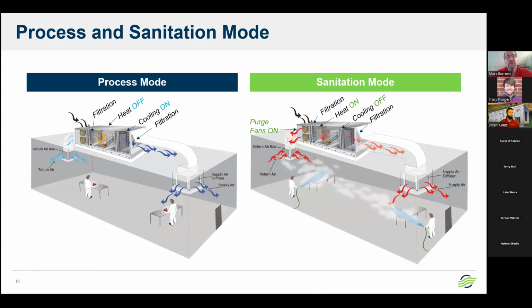So again, the process mode, 5% outside air. We're going through the pre-filter, which is a 2-inch pre-filter. The heating is off. The cooling coil is definitely active, and we're going through the filtration. If you're taking notes on this, on a wet coil, we don't like to go more than 600 feet per minute on the cooling coil. If we go above that, the fear is we're going to blow water off into the airstream.